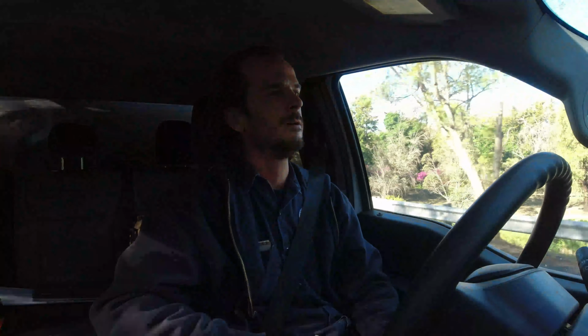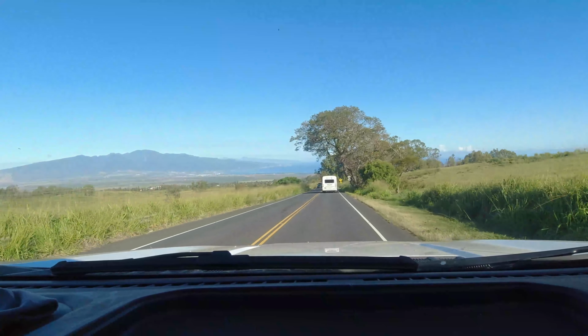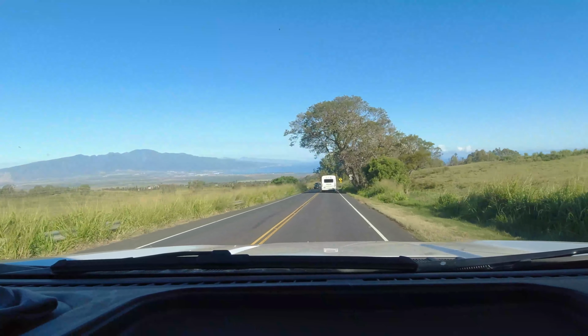We'll do the same checks. We'll look at the amps. We'll listen to it. Probably do a thermal scan with my FLIR, and we'll go from there. There's a chance they started it this morning and it seemed to be working. However, it was loud. There's a chance though that it has faulted in the time in between we got dispatched this morning and when I arrive. So if it's faulted, then we can look at that. If it hasn't, it may just be, okay, everything looks good, let's run it to fail kind of vibe. So we'll look at all our options when we get there, and I'll see you there.